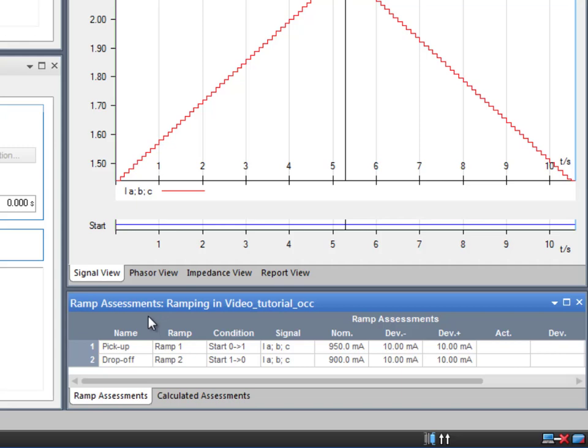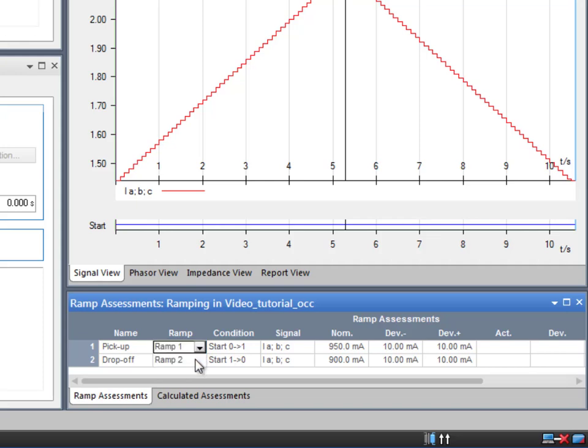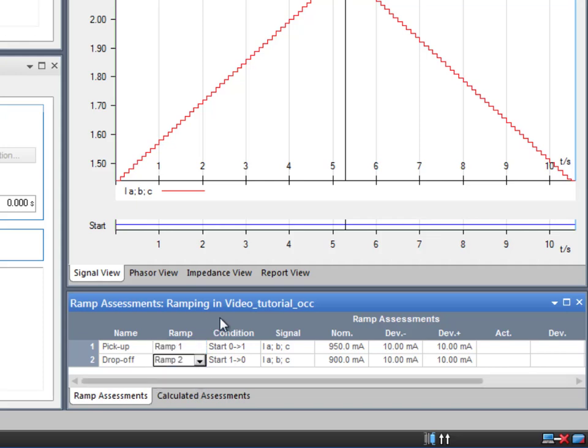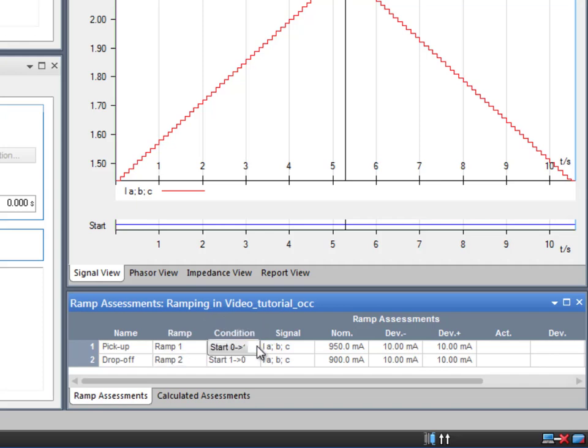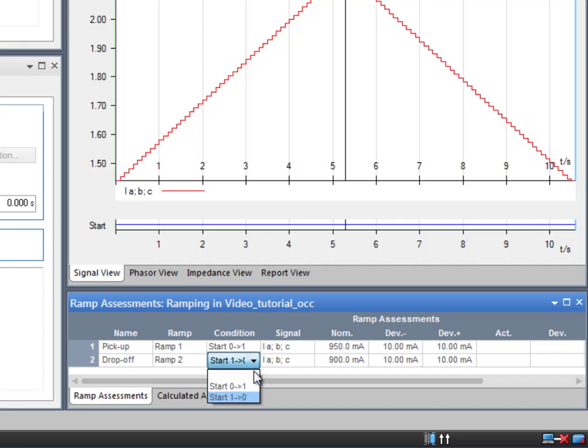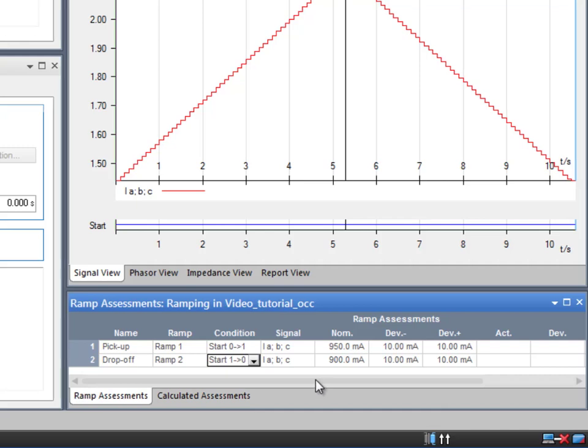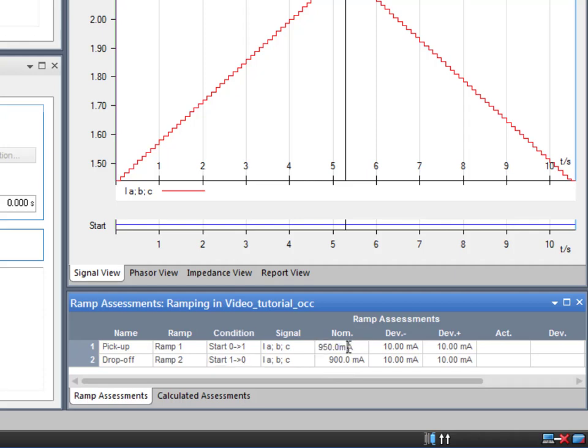The ramp column shows the ramp state in which the measurement is performed. The pick up will take place in state 1, while the drop off will take place in state 2. The condition column reflects the condition to start the measurement. We will measure the pick up value when the start contact switches to 1 and the drop off value when switching to 0. The nominal value is the expected value, 1.8 amps for the pick up. According to the relay's manual, the drop off value is around 0.95 times the pick up, which makes 1.71 amps.